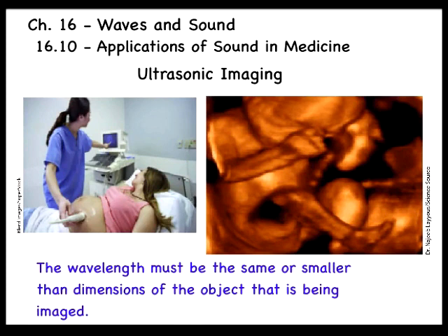For instance, the wavelength of 5 MHz ultrasound is λ = v/f, which equals 0.3 millimeters if a value of 1,540 meters per second is used for the speed of sound through tissue. A sound wave with a frequency higher than 5 MHz and a correspondingly shorter wavelength is required for locating objects smaller than 0.3 millimeters.